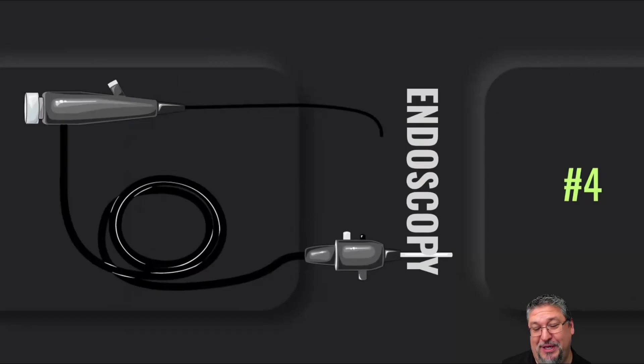My number 4 is endoscopy. Just like with the IUSS, it's one of the first things a surveyor is going to want to see when they come in. They're going to want to see those flexible endoscopes because, in national patient safety goals, it almost always shows up in the top 5. We have a lot of infections associated with damaged or improperly inspected endoscopes. We've seen outbreaks with the water lines coming into the AER. So there are a lot of issues with endoscopes, and they are going to be looking at that area very heavily.